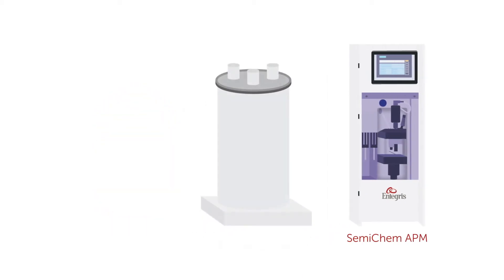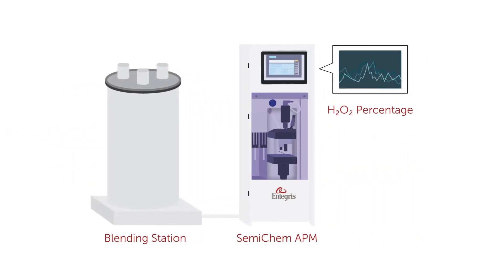First, electrochemical analysis happens during CMP blending using the Semi-Chem Advanced Process Monitor. The Semi-Chem Monitor connects directly to the blending station and automatically samples, analyzes, and provides data that helps control slurry composition.